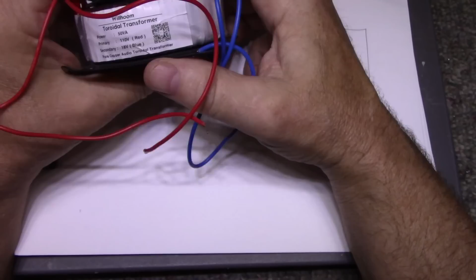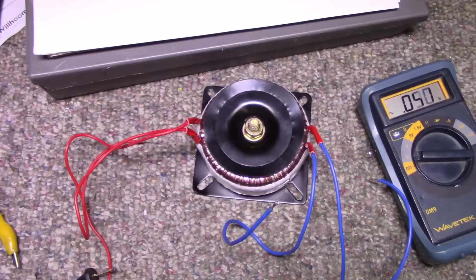Okay, first thing we should do is test this transformer, put 120 volts into it and see what we get out. This thing says it's wound for 110, but I'm going to be feeding it 120, 122 right now, so it's going to be over voltage. That's why I think I should have gone with a 15 volt transformer instead of an 18, but we'll see how this works. Let's hook this up to power and see what we have for a true reading on the secondary.